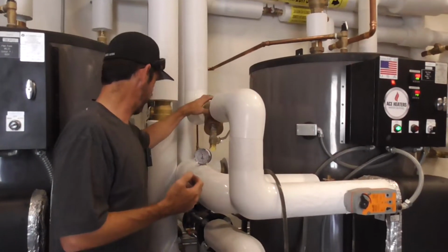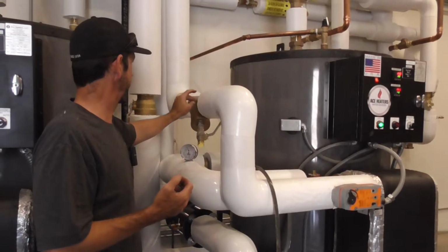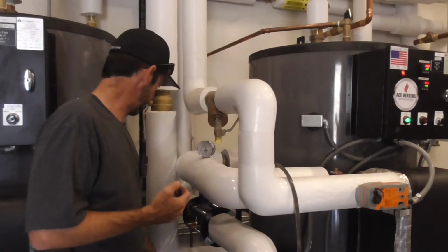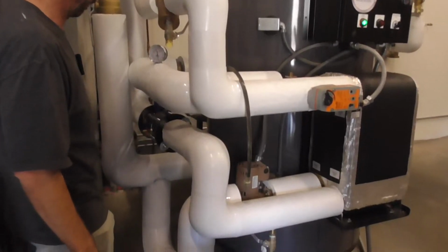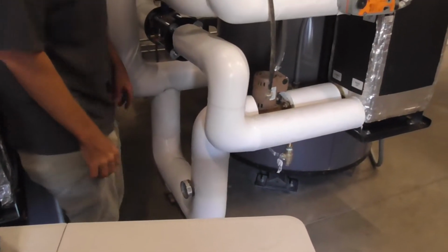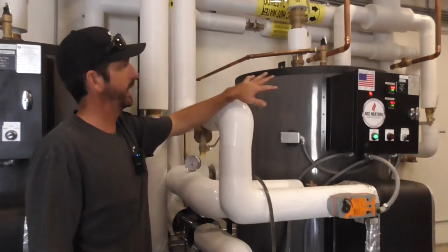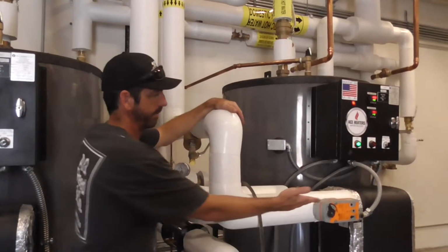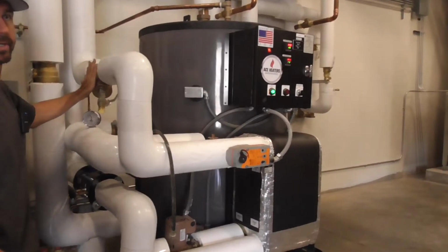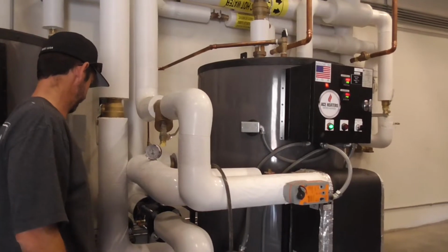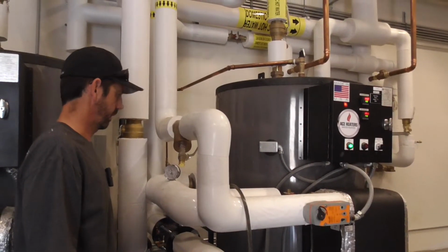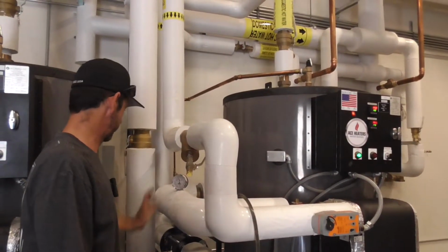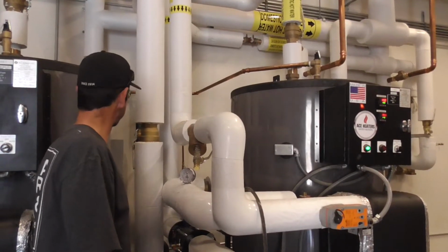Strainer. There's a strainer on the heating hot water side up here, and then there is a strainer down on the domestic side of the bottom over here too. Okay. So if you're not making your temperatures and the valve is open, we can start looking at a strainer over here. And if that was good, we'd want to check the strainer at the bottom too.